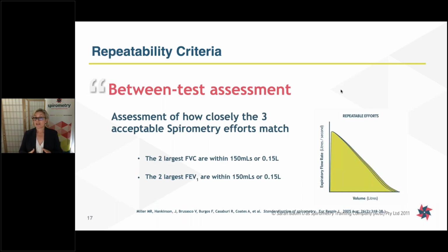Repeatability criteria is when we look at our 3 good tests and decide how closely they match. We can overlay the curves and that gives us a little impression of how closely they match, but what we also do is look at the parameters. We observe the 2 best FVC and make sure they match within a certain volume range of 150 mLs. And we're also looking at the 2 largest FEV1, making sure they match within 150 mLs as well.